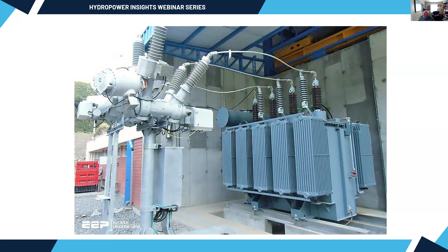And then once you generate hydropower, what are you going to do with it? Generally outside the powerhouse, there'll be a transformer for each unit, each generator. Transformers are devices that either boost voltage up or drop it back down, because lower voltages have more loss in transmission, basically friction through the wires. So you boost the voltage up. You get 11,000 volts out of the generator, and it goes outside to this transformer.